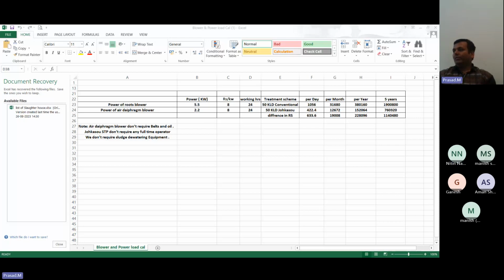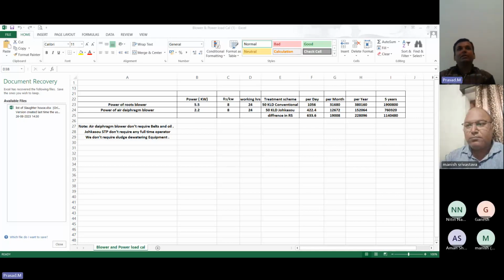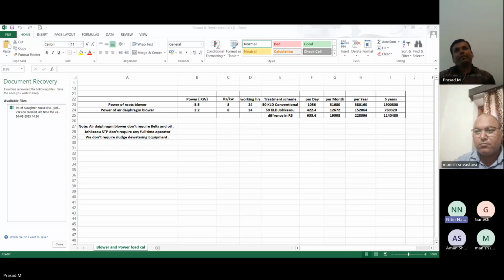नहीं अभी सर क्या है, दोनों एक चीज है कि एसटीपी एक बार आपने कमीशन किया तो वो कंटिन्यू चलना चाहिए. बराबर है. But अगर एसटीपी आपने लिया और 3 महीने के बाद चालू कर रहे हैं तो वो प्रॉब्लम नहीं है. बट एसटीपी कमीशन करने के बाद उसको अगर सीवेज नहीं दिया तो वो प्रॉब्लम है. ओके. तो मीन्स आपको वापस रिकमीशनिंग करना पड़ेगा. अच्छा, because I am talking about that marriage gardens.